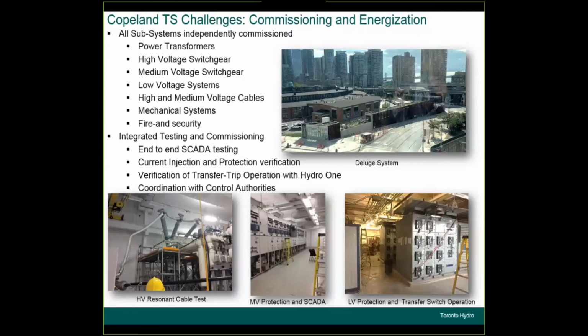A couple of pictures here. I'm showing the HV resonant cable test. That was a significant challenge. We established that we would test the cables once they were installed and had to modify our high voltage switchgear. This is Siemens HVGIS, where we've removed the voltage transformers and installed bushings to enable us to test both the connecting cable to Hydro One and the cable that feeds the transformers.